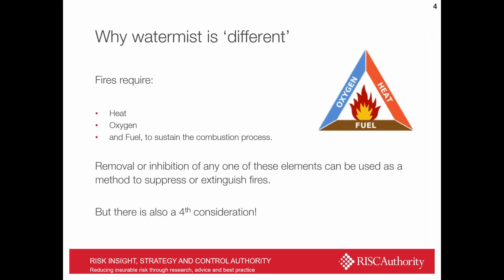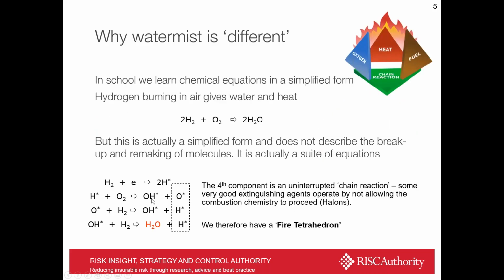So, first of all, why is Watermist different? I do apologise for putting up a picture of the fire triangle. Nearly every talk on fire starts with it. But I'll be as succinct as I can. We all know that fires require heat, oxygen, and fuel to sustain combustion. And so any suppression system that comes to the fore is going to act on one of those. But it's actually a little bit more complicated than that, because we also need to consider the chemistry of combustion. So you may be more familiar with the fire tetrahedron. And really this is about interrupting the chemistry of the combustion process itself.